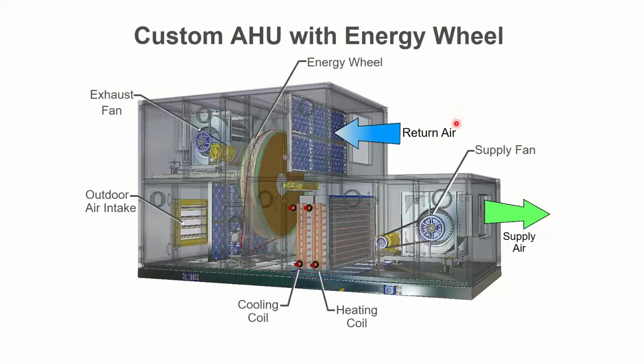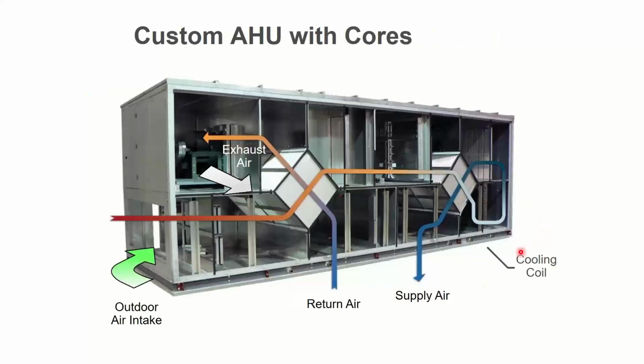So it looks like this on the inside, right? So return air goes through, it gets filtered. You have to filter the air before it goes to the heat exchangers of the ERV because I don't want to have to clean those because that's a pain, right? I want to clean them minimally. Filter, ERV, where it gives up or takes BTUs, sends the dirty air out. Fresh air comes in, goes through the filter on this side. I've got to filter both sides of the ERV. It picks up the BTUs that this guy dropped off, and it comes in and gets heated further if needed and moves its way into the system. There are some quirks that you might see too.